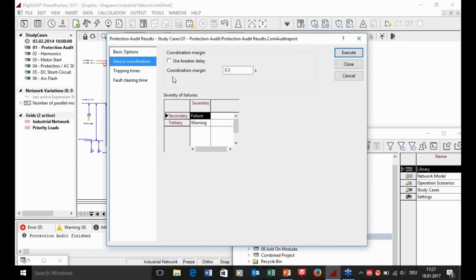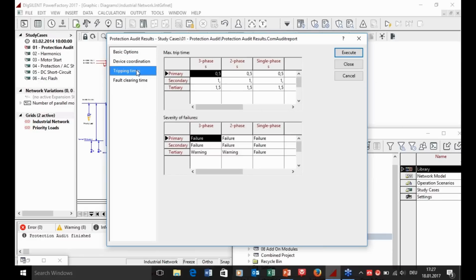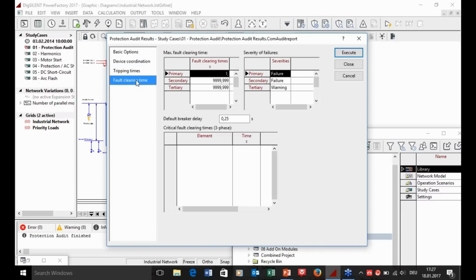The verification of device coordination checks that there is sufficient interval between the primary, secondary and tertiary protection operation. Here, as in all the reports, the severity of the case where a criterion is not met can be defined. The tripping times report verifies the protection operation times against given criteria. The fault clearing time report also takes into account breaker operation times, and a default value can be supplied. The reports are now executed.